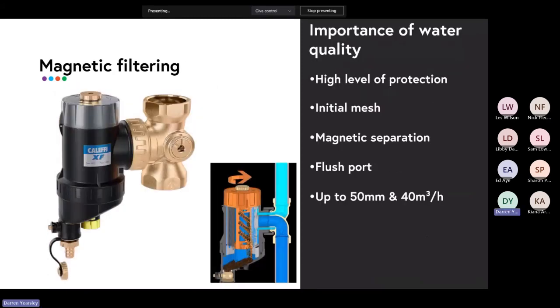Okay, so water quality across a plate heat exchanger is always fairly important. So we do magnetic straining on the primary side. Again, the water that goes through the appliance is reasonably limited. So you might have 300 or 400 litres of water in the system, your buffer, your primary mains, your plate heat exchanger, and then to your appliances.